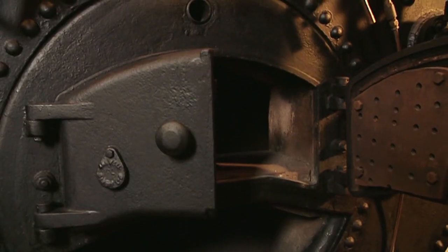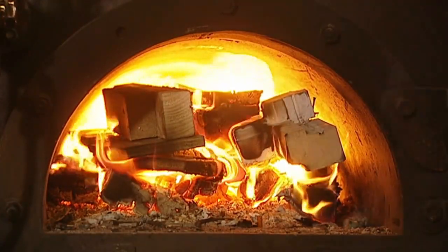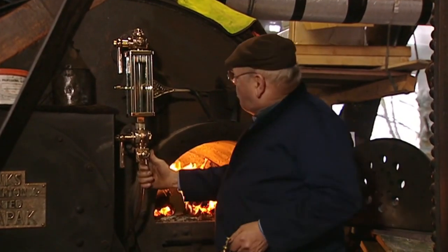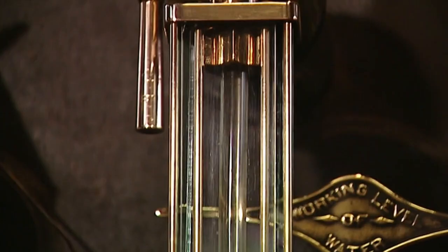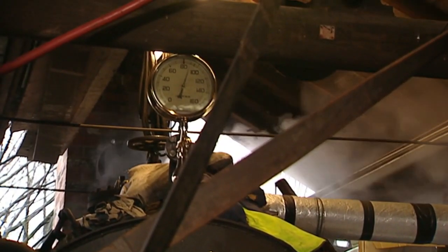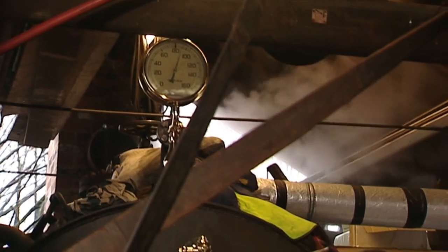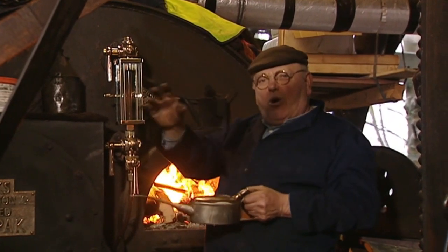You only have a fire in here a few times a year, but at home I've got steam up most of the time. It's very important to know where the water level is, and this particular bit here is the water gauge. When you open the valve at the bottom, the steam pressure inside fires the water down, and when you shut the valve, it's forced in at the bottom by the water pressure below the steam and you can see it rise up again. A bit higher up is the pressure gauge — it's a great clock with a steel spiral tube inside it that, when it gets up to pressure, works a quadrant and a rack and registers on a needle the pounds per square inch in the boiler.